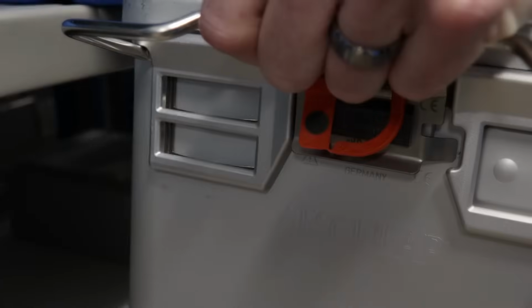But what about containers? Sterilization containers will usually have multiple outside indicators, which can be found as dots on the filters or even dots on the locks or tamper-evident devices. These locks not only show whether a seal has been broken or not, but it also has that dot for easy reference of sterilization. Some people might think those different indicators are good enough to prove sterilization, but wait, hold on a sec. That only proved the outside of the tray came into contact with heat or a chemical sterilant. It doesn't show whether the steam or chemical sterilant made it inside of the tray to actually touch the instruments themselves. That is where internal indicators come into play.